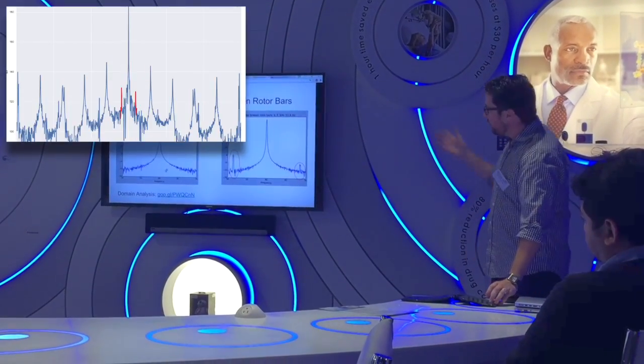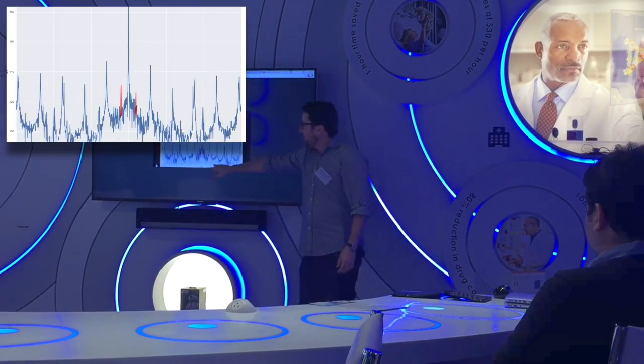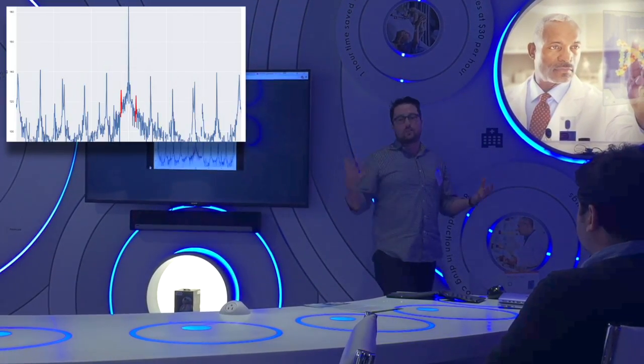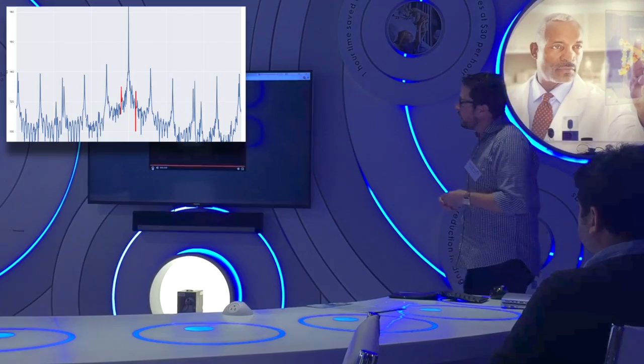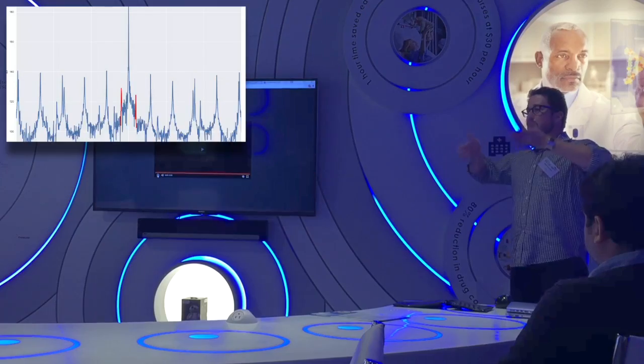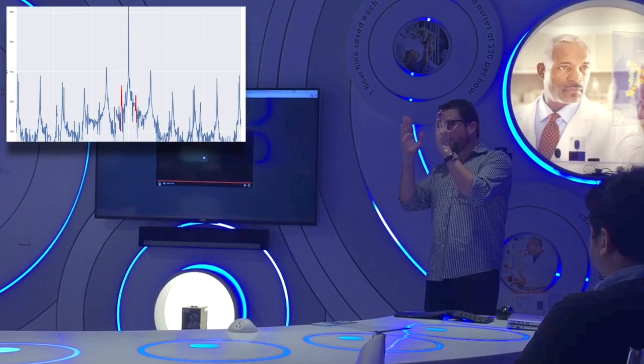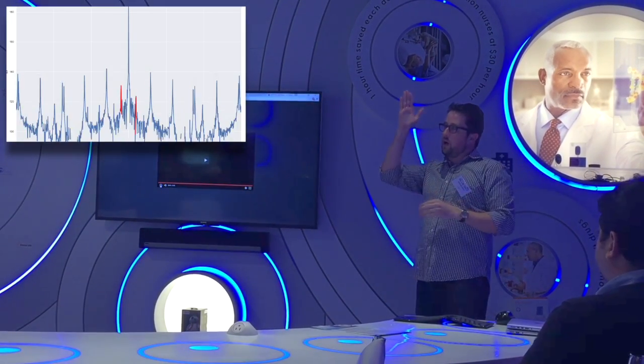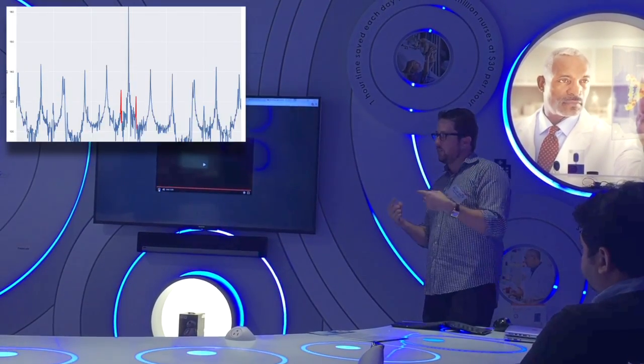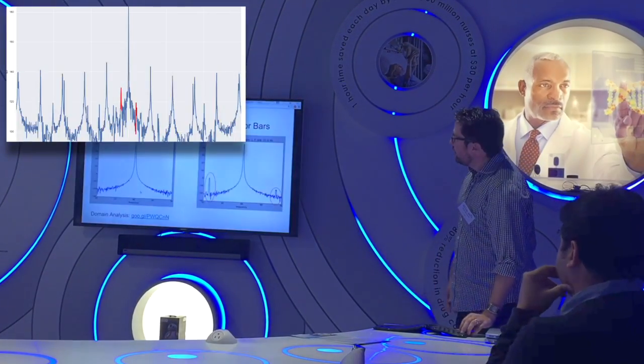And so again, I have an animation of that same motor in Livingston with that frequency band highlighted here. Essentially what you see is there is a little bit of an aberration, but it's not large enough to rise to the level of a failing motor. And so although there would be no alert generated there, what the system would do is continuously monitor that and watch for those changes. And so look in that frequency band and say okay, we're at a certain level, we're gonna watch if it goes up or down. And as it starts to go up, signifying that a rotor bar is failing or it's completely failed and maybe that failure is starting to cascade, we can track the degradation of that motor in real time and alert those building operators.